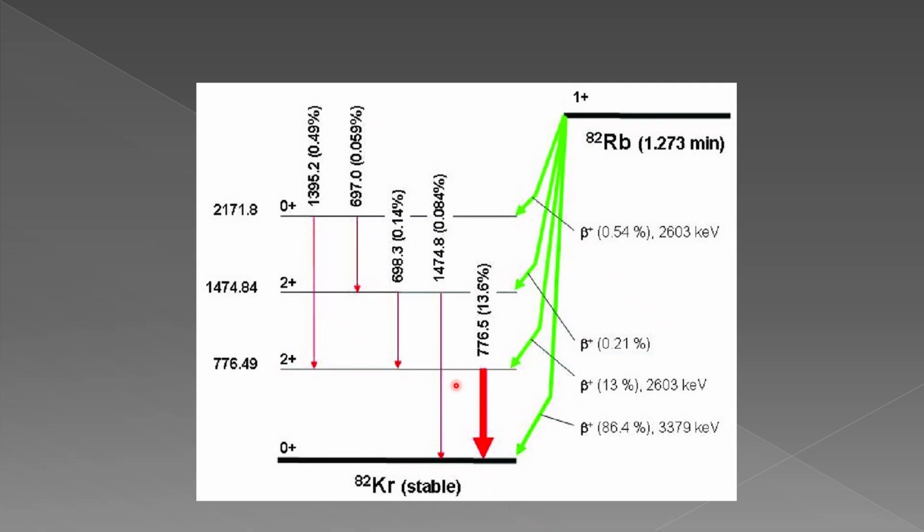And because the half-life is only 75 seconds, if you're using it for cardiac PET, you have to have a rubidium generator right beside the camera. You do QC in the morning to make sure it passes, and then the generator gets eluted straight into the patient and you image right away. Typically, if you spill rubidium, they say to just clear the room for about 10 minutes and it'll be decayed. So 10 to 15 minutes and it's gone through all its half-lives. So you would still, of course, want to survey, make sure it's gone, but those patients don't stay radioactive for very long.